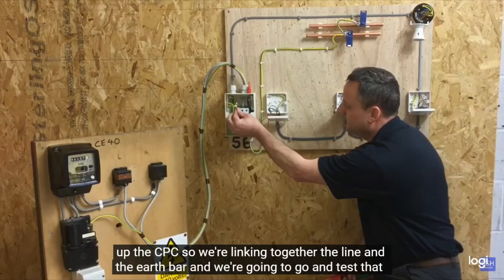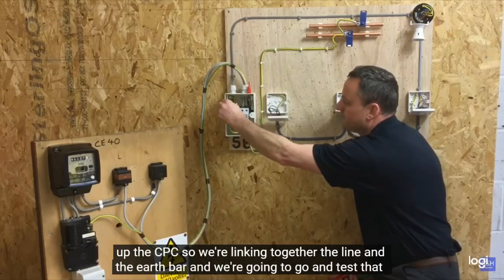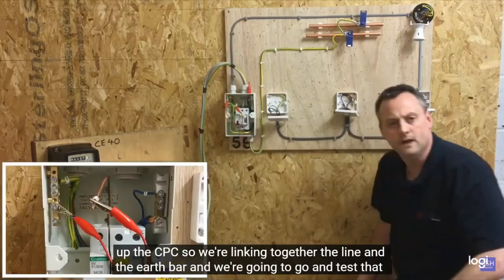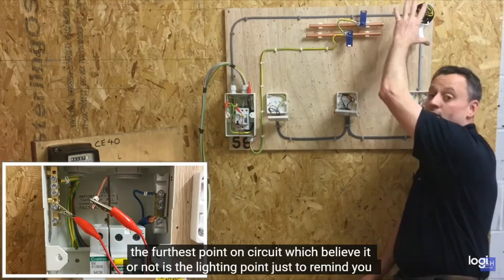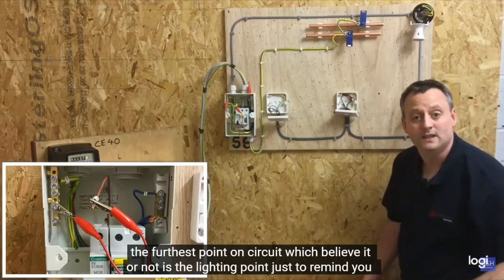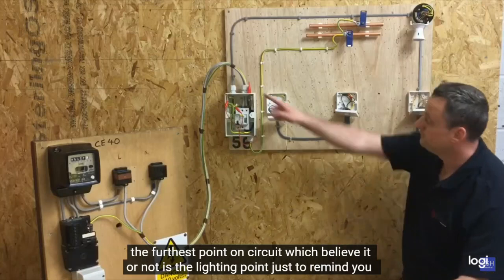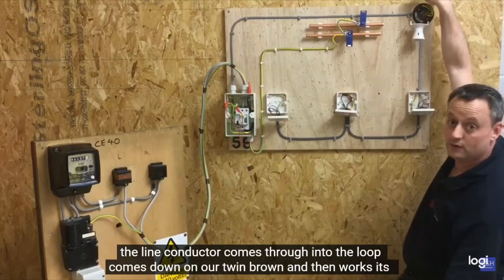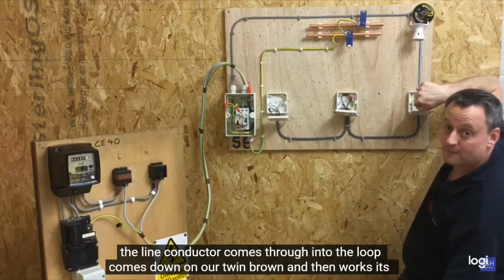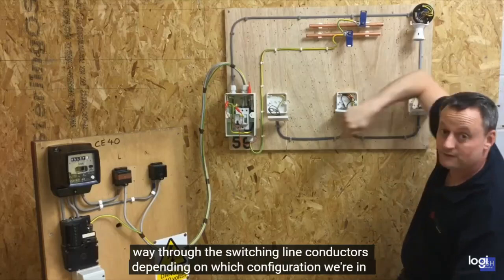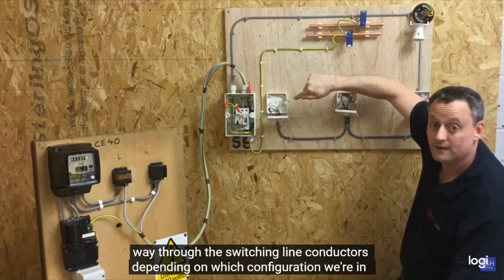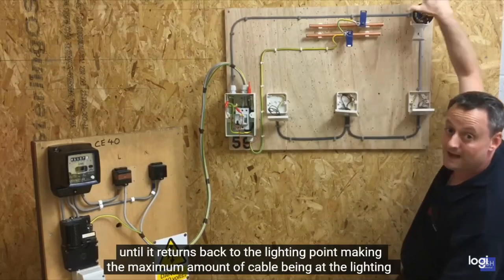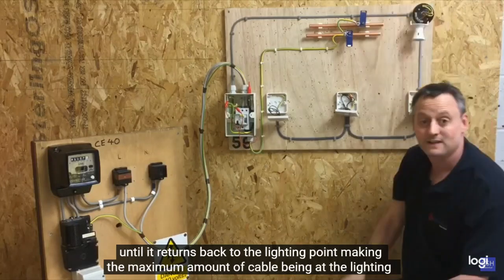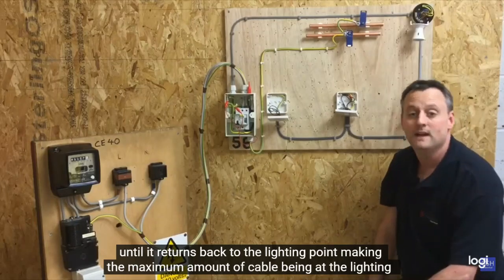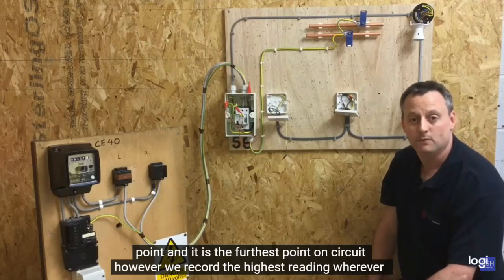Just to remind you, the line conductor comes through into the loop, comes down on our twin brown, and then works its way through the switching line conductors depending on which configuration we're in, until it returns back to the lighting point, making the maximum amount of cable at the lighting point, and it is the furthest point in the circuit. However, we record the highest reading wherever we achieve it, and we should see when testing the lighting point that our reading will change depending on how much of the switching circuit we have in.